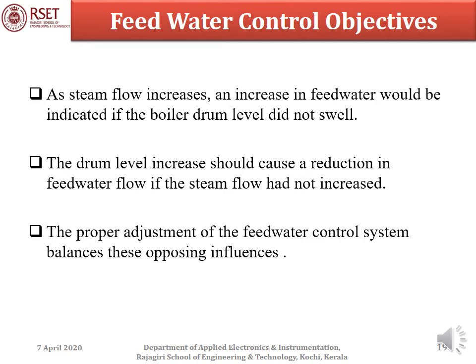These influences act in opposing ways. In the first case, with no swell and increasing steam flow, feed water should increase. In the second case, with constant steam flow but increasing drum level, feed water should decrease. Since swell is not absent and steam flow is not constant, the control must find a proper balance based on which factor is more important at any given moment.